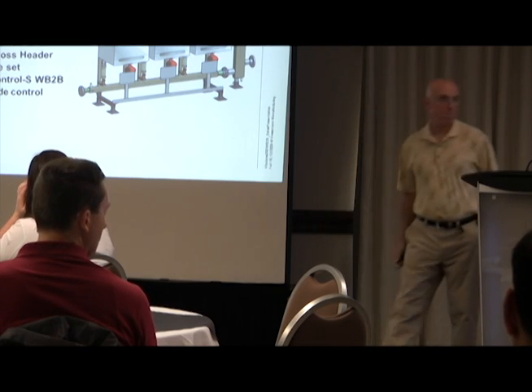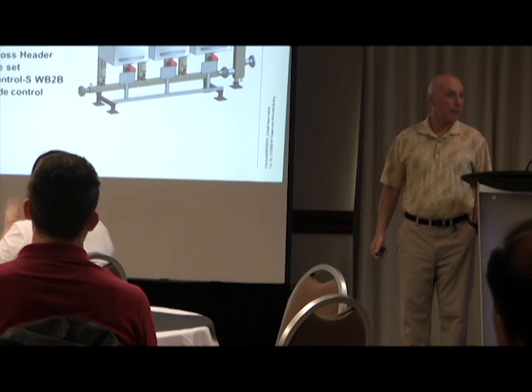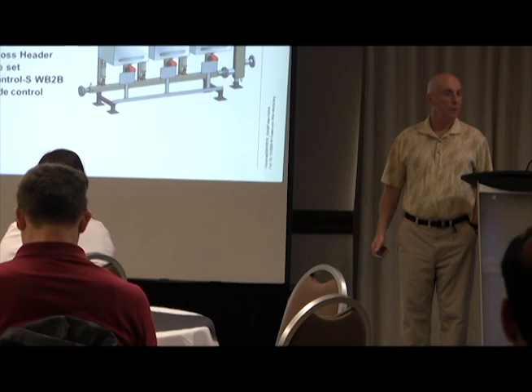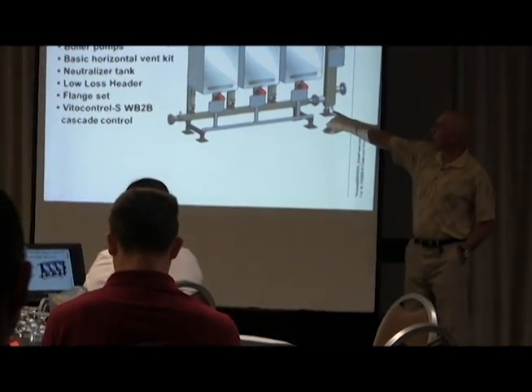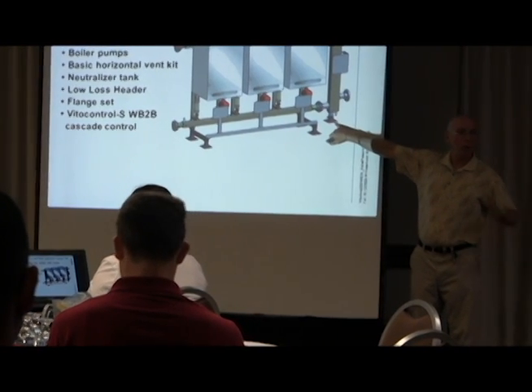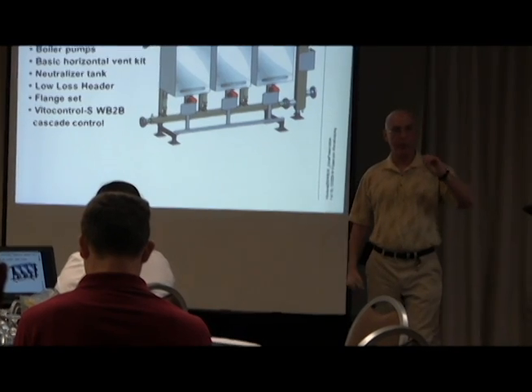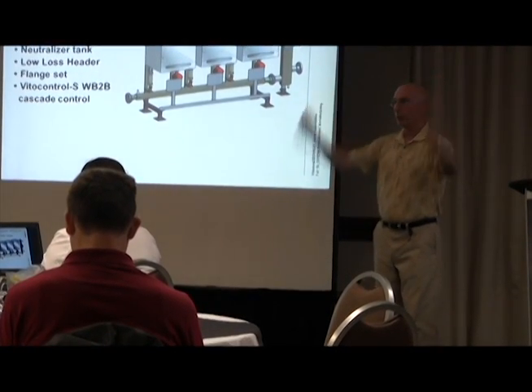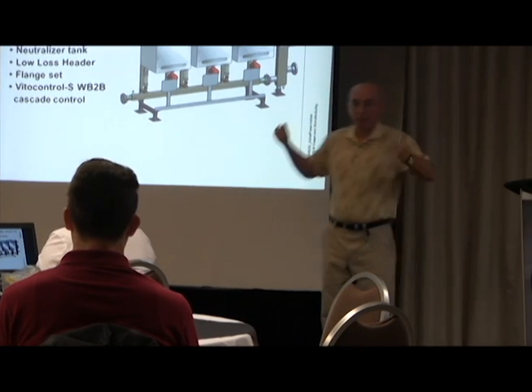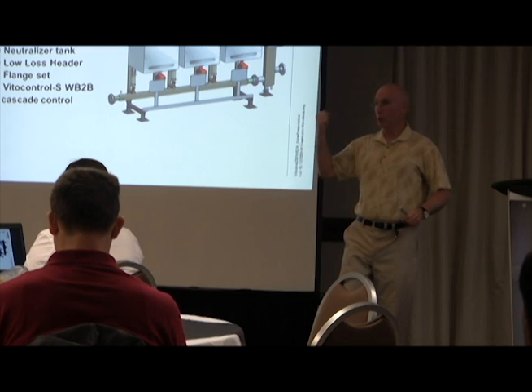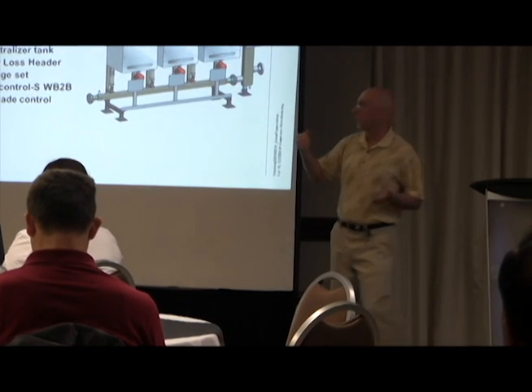So Tom, just to expand on that, those are high efficiency condensing boilers? Yes, absolutely. So if you had an old system and you wanted to be sure that you didn't contaminate the boilers with the inability perhaps to properly clean out the existing system, could that be isolated via a heat exchanger? Well, that's another really good point, because the low loss header, if you look right down at the bottom in the picture here, it's actually one of the advantages of putting it on. Usually when you're doing a retrofit and you drain the water out of a system, then you fill it back up, and you got maybe a bigger pump on it, and suddenly you're circulating maybe more sludge that's in the system.